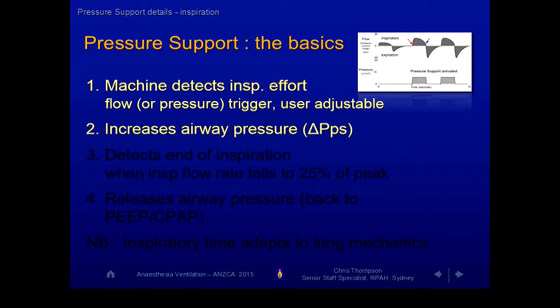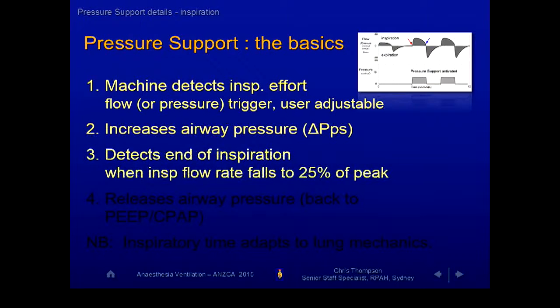The increase is set by you, the pressure support value. The really clever bit is that the machine then watches the airflow curve until the airflow drops to, say, a quarter of the peak airflow. So you breathe in, your flow rate slows off, and when it drops to a quarter, it says that's enough, you've had most of the air, I'll stop now, and it drops the pressure support out. So it's dynamically adjusting the duration of that increase to match what the person requires.